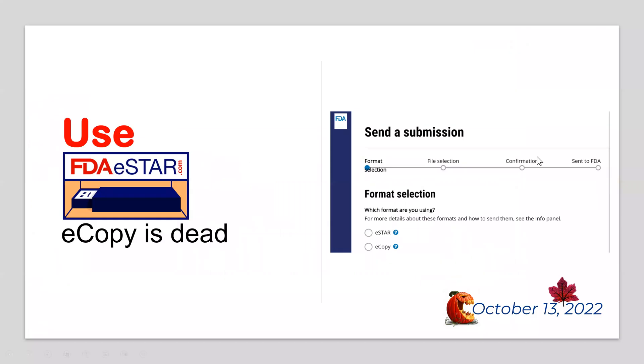This is a new video about the 510k E-STAR process. FDA eCopy is our old email submission method that we've been using. We're going to continue to use that for the next year, but the FDA has officially announced that FDA E-STAR is going to be the new required template as of October 1st, 2023. So we've got a one-year transition.